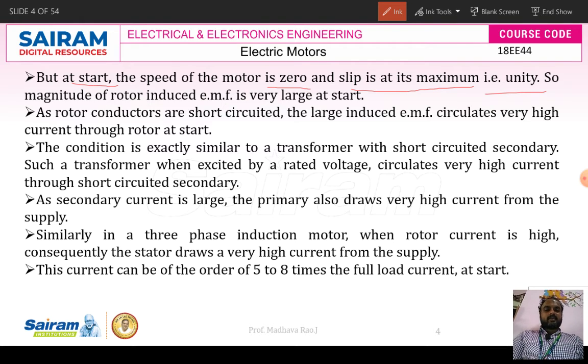This condition is exactly similar to a transformer. A transformer has two circuits, the primary winding and the secondary winding. Similarly, an induction motor has a stator winding and a rotor winding. A transformer with a short circuited secondary, when excited by rated voltage, circulates very high current. The secondary current is large, and the primary also draws very high current from the supply. So it acts like a short circuit test on a transformer.